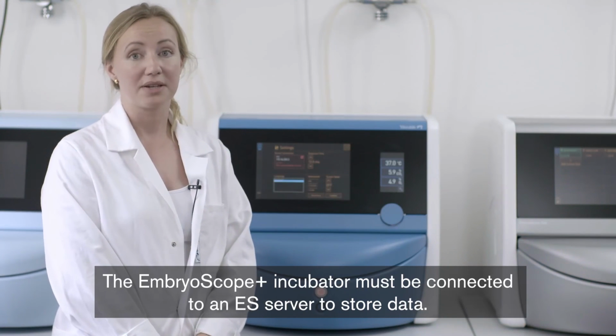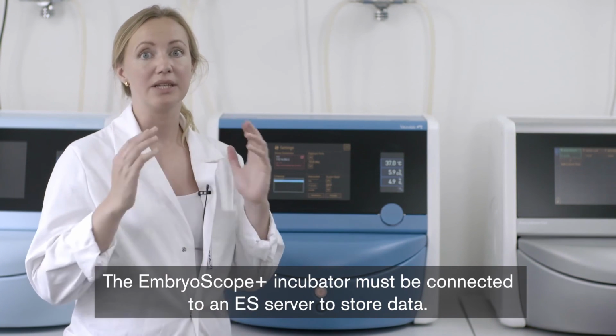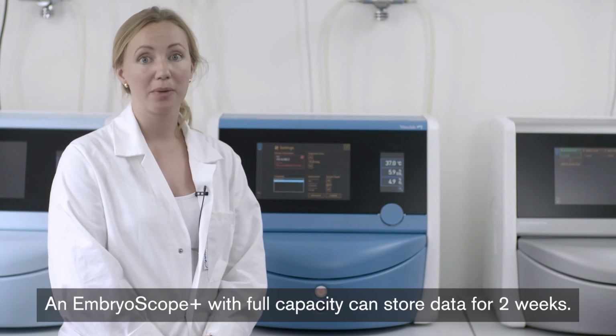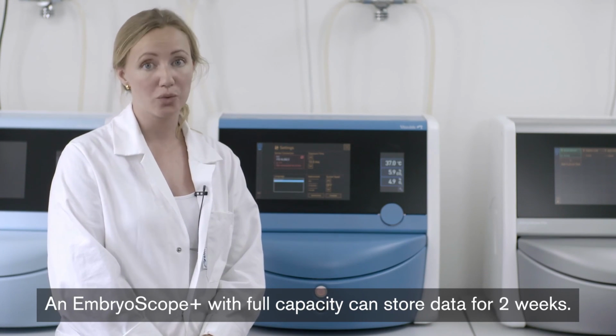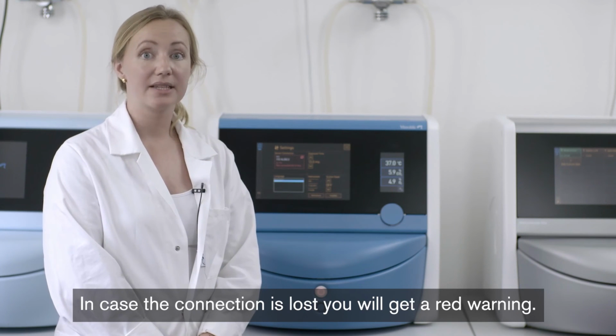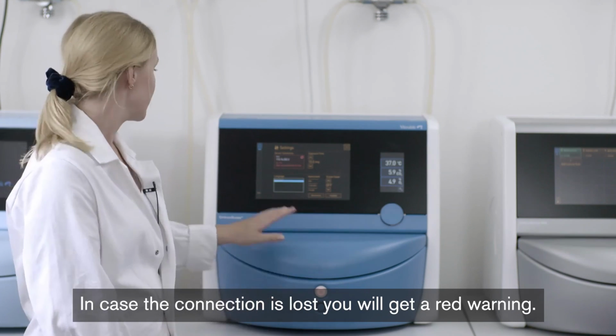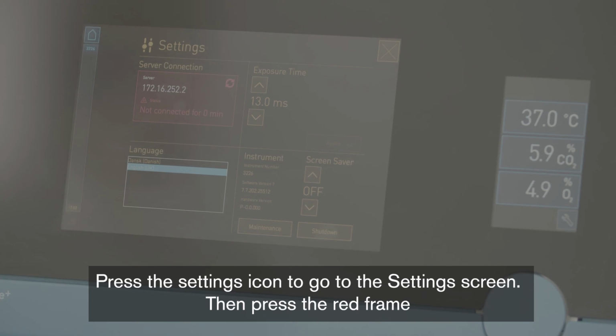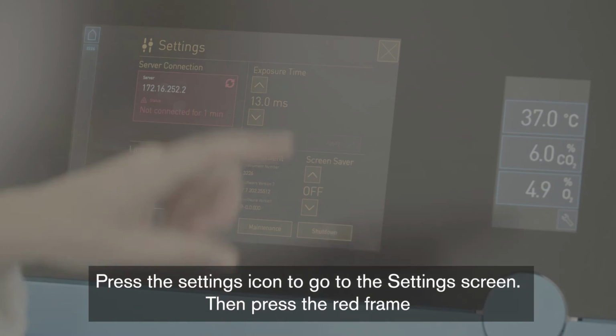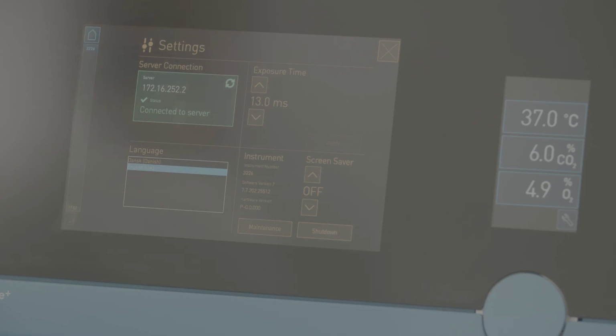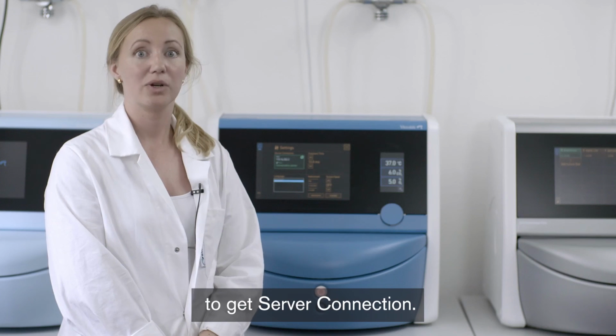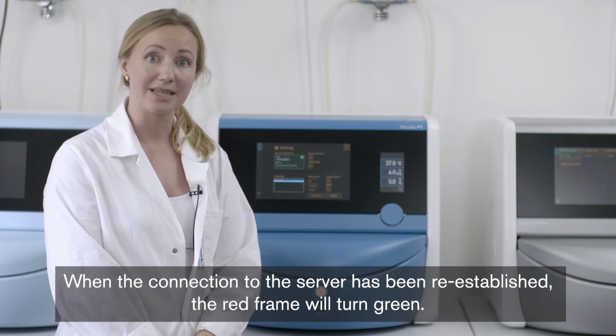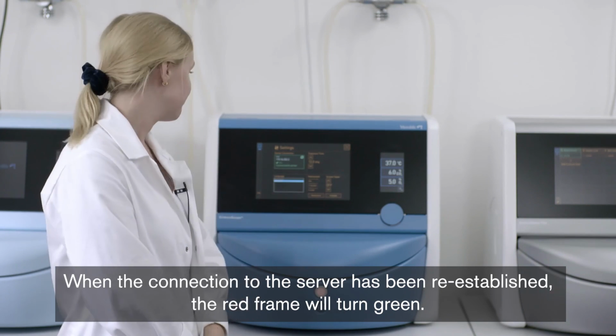The EmbryoScope Plus incubator must be connected to an ES server to store data. An EmbryoScope Plus with full capacity can store data for 2 weeks. In case the connection is lost, you will get a red warning. Press the settings icon to go to the settings screen, then press the red frame to get server connection. When the connection to the server has been re-established, the red frame will turn green.